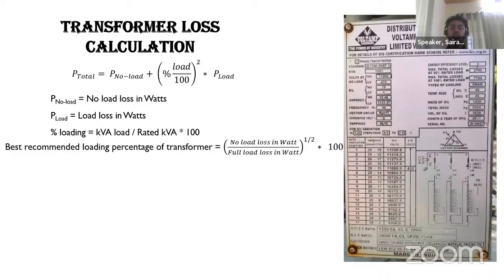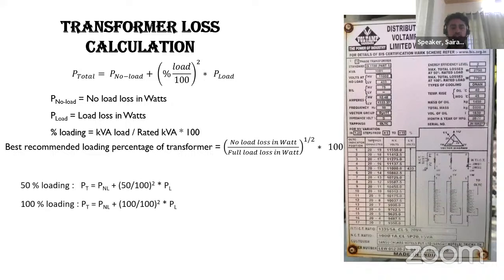The best recommended loading percentage of the transformer is found using the formula: the square root of no load loss in watts divided by full load loss in watts, multiplied by 100. You will get the result in percentage. For the nameplate of the transformer given here, I have calculated the load loss and no load loss and presented the best recommended loading percentage here. Let us have a look.